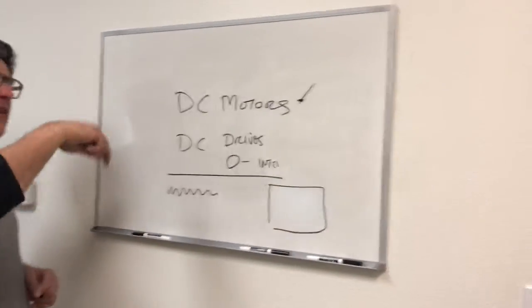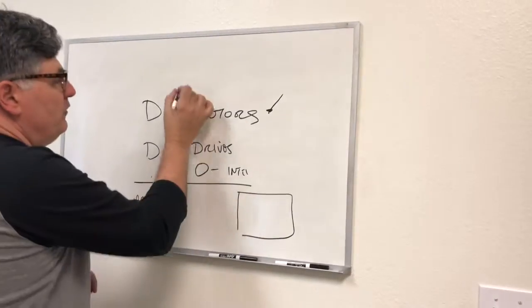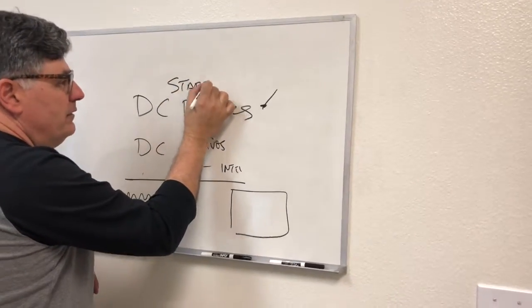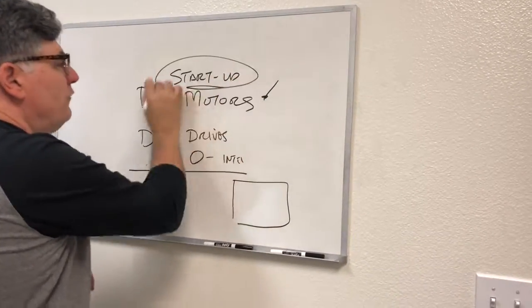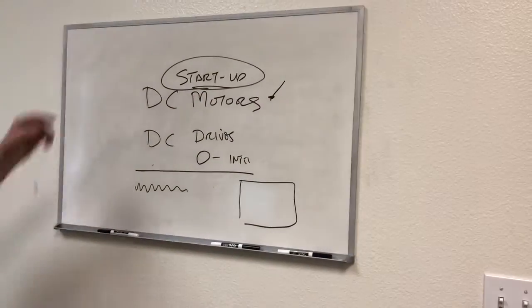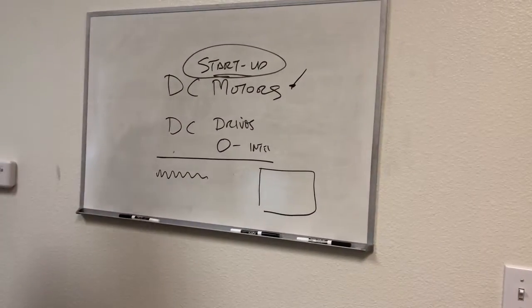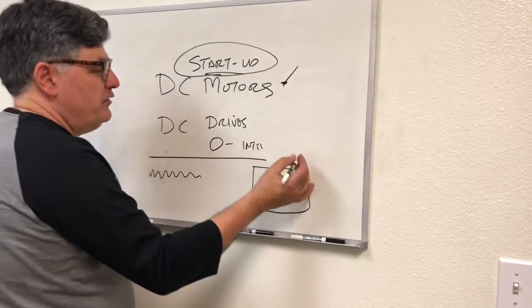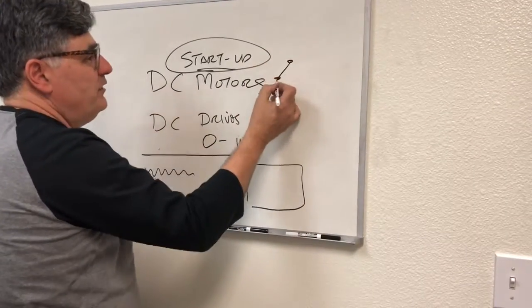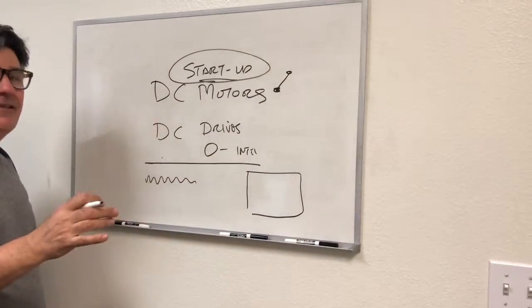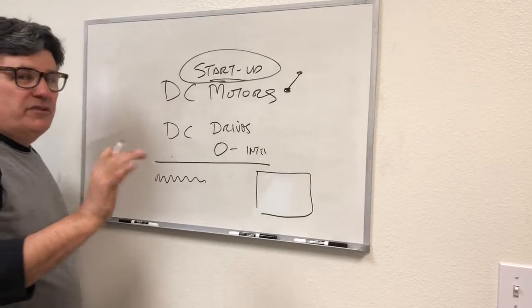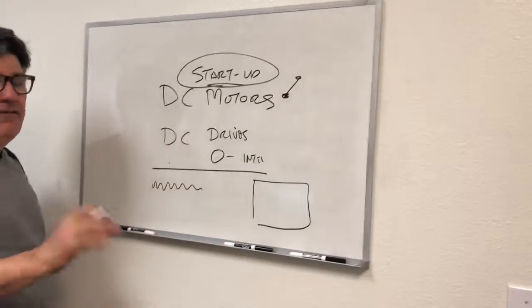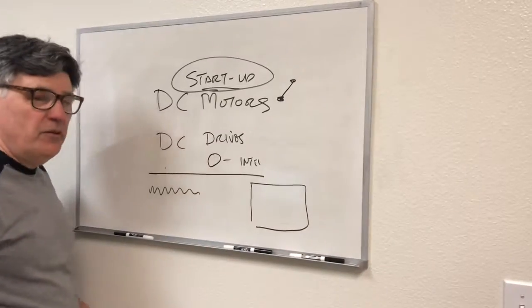Now mind you, these other companies are going out to the field and doing startup. That's the difference - they're going to the field and charging an enormous amount of money for startup, because they're bringing their own communications cable and resolving it. They've got the instrumentation required to minimize - which is the key word, not eliminate, minimize - the VFD effect that's having on the probes and the interference.